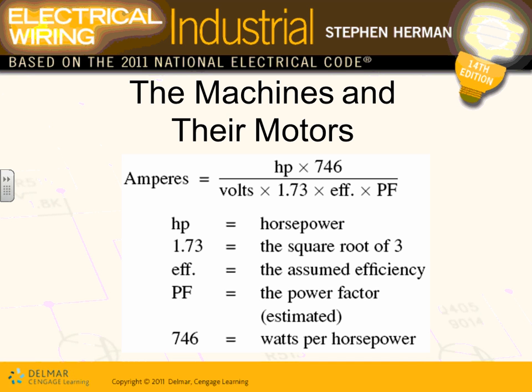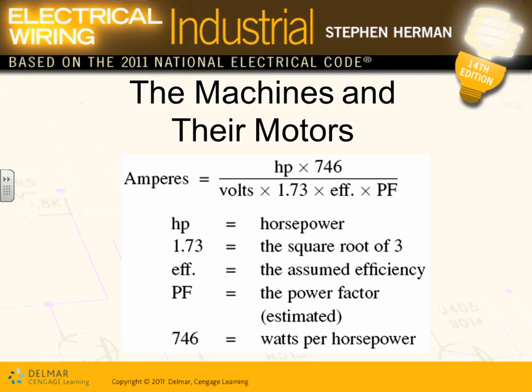You take the horsepower of that motor, multiplied by 746, divided by voltage times 1.73 times efficiency times power factor. This, Jeff, is called the full load current. That's how we find the full load current of a machine. Not the NEC code book current. This is the full load current. So look at the power factor and the efficiency. The power factor, and efficiency, and horsepower will be a decisive factor.